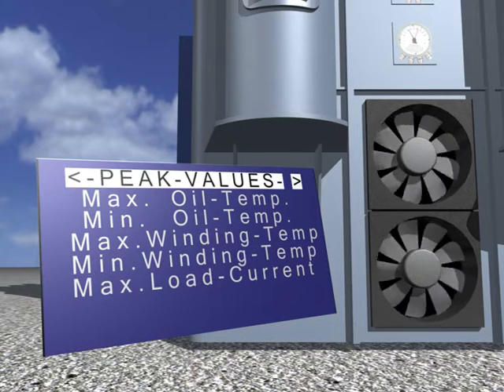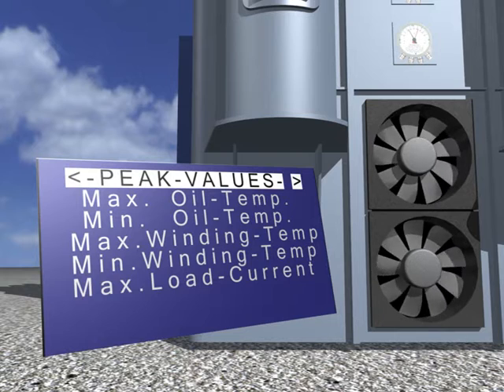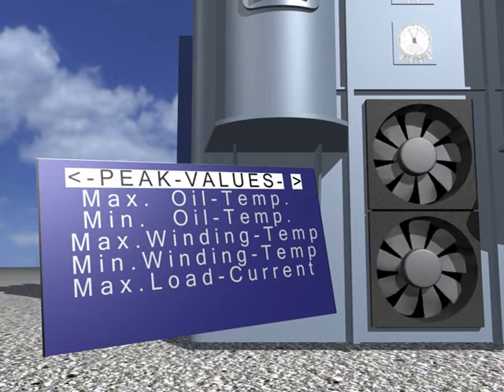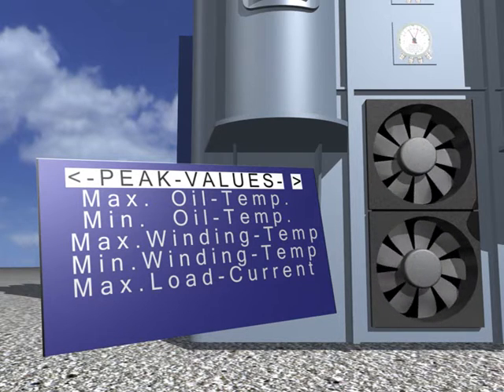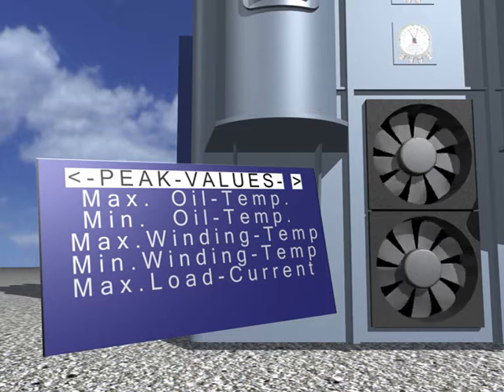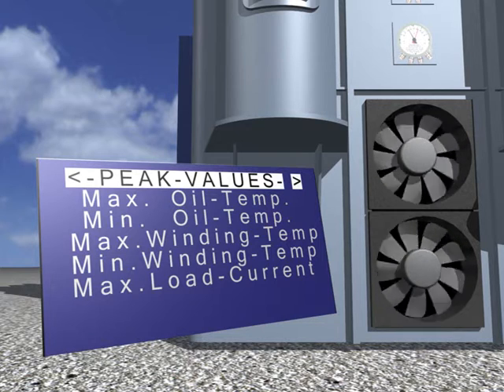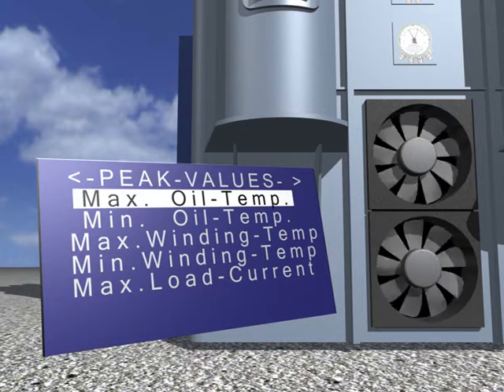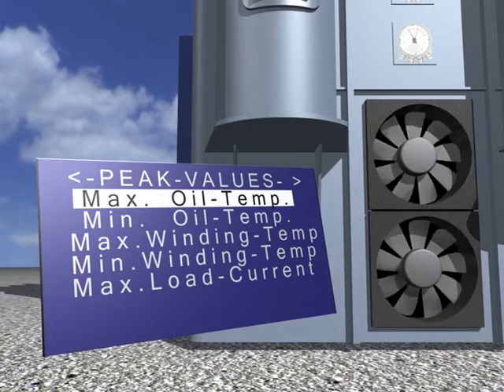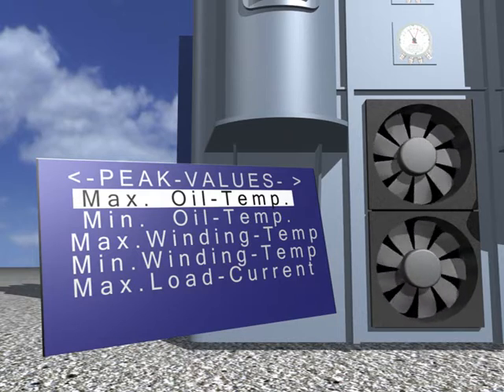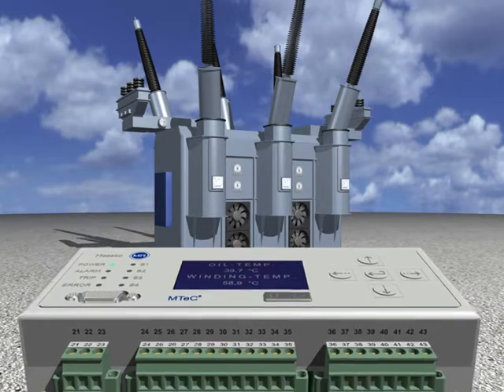For correct forecast of future temperature peaks, accurate knowledge of the past is necessary. The menu item Peak Value is an easy-to-use version of the mechanical drag hands. Min-max values for the oil and winding temperature and the maximum load current are logged and indicated.